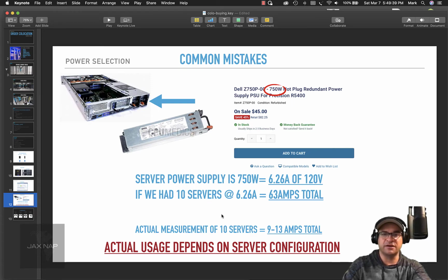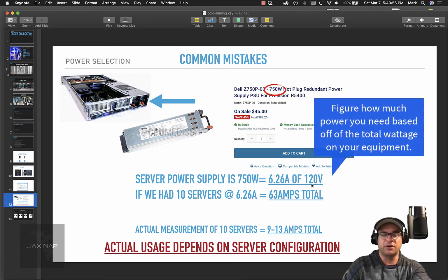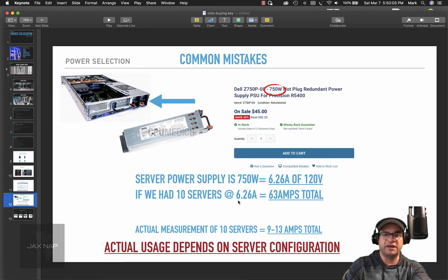But for the sake of what we're trying to show you here, don't worry about that. The server power supply is 750 watts, so it takes about 6.26 amps at 120 volts if you size it per the total consumption. If you had 10 of these servers, assuming they took 6.26 amps per server, that's 63 amps total. That's where people mess up really badly when sizing up and trying to figure out how many whips they would need, because at 63 amps you'd have to get two 30 amp 208 circuits, which is going to cost you probably about $2,000 a month, depending on what data center you go to.